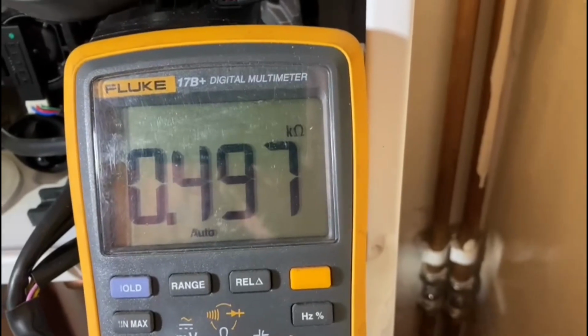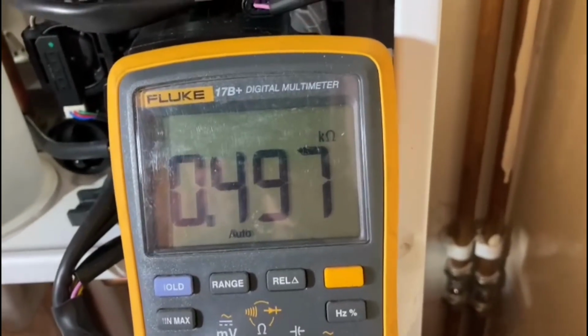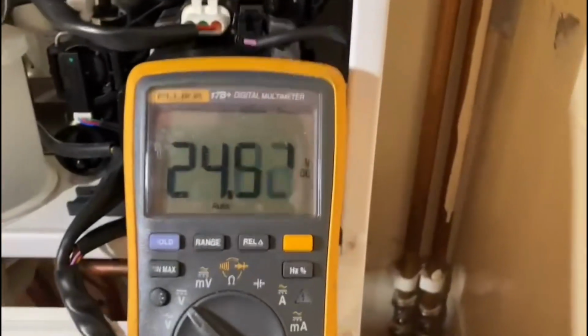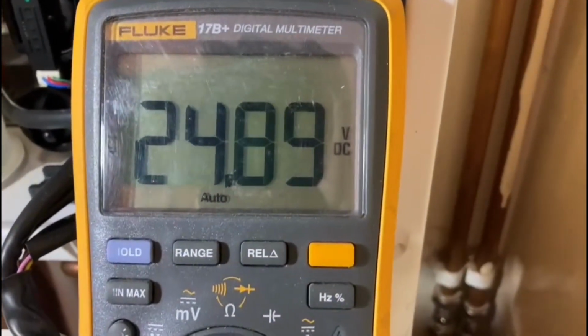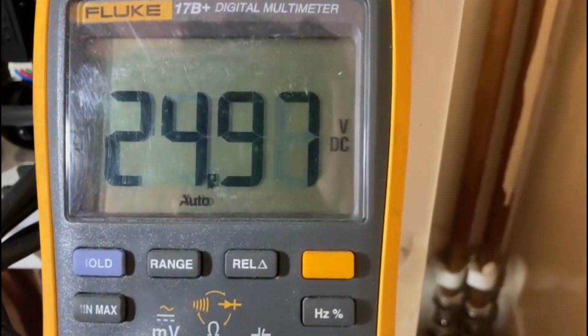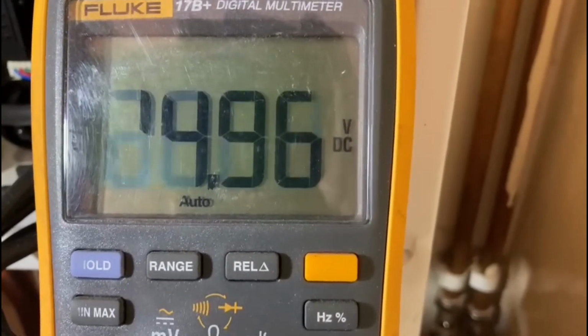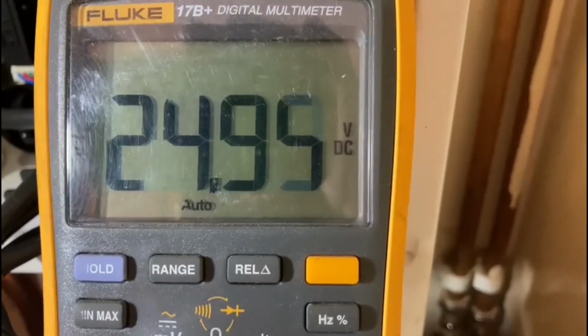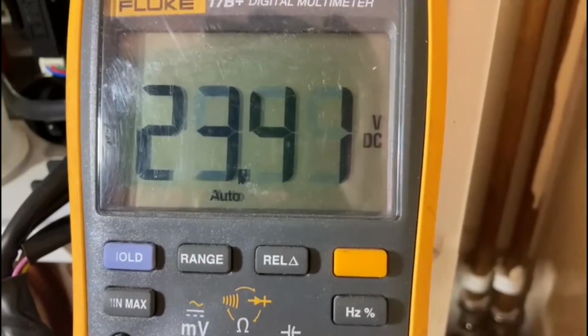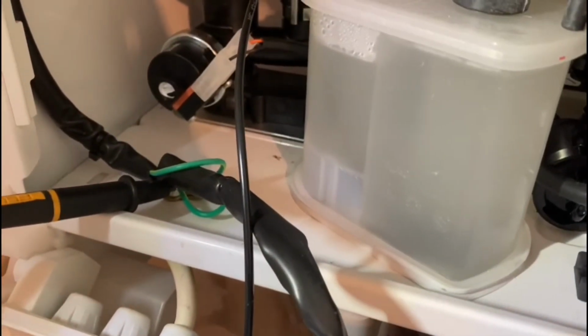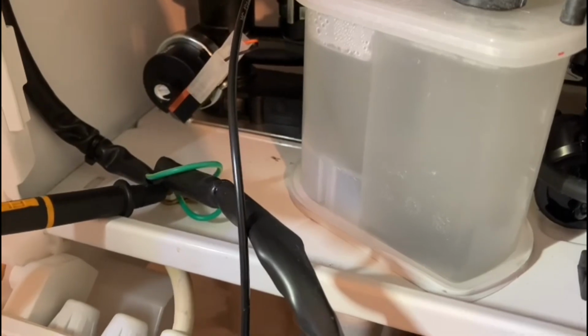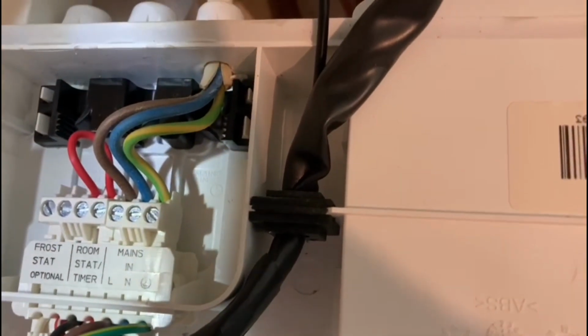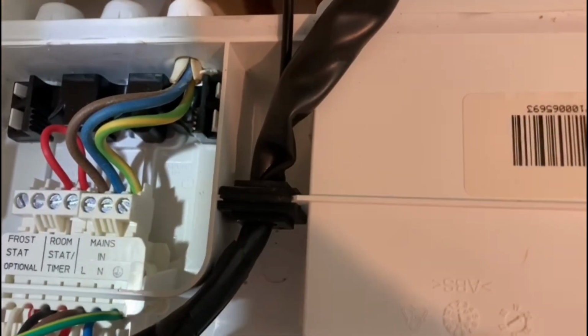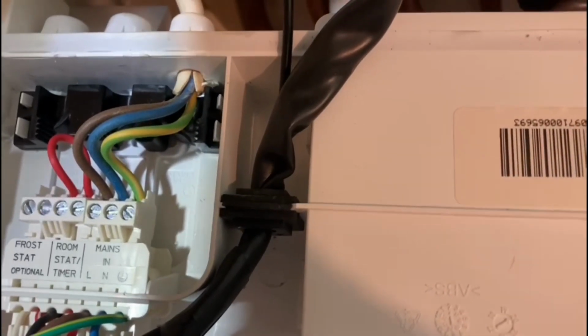I'll show you how to test the power voltage to them now. Give me one moment to set that up. I'm on voltage DC. Because I only have one hand to hold the camera and show you this test, I've had to jam my one probe on the earth strap of the boiler. You'd normally use a neutral or earth on the incoming supply, but they're too far apart for me to hold with both hands.